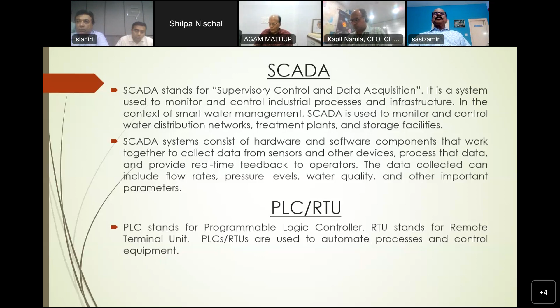A typical SCADA system for a water supply network covers areas like water levels, hydraulic pressure, motor speed and temperature, pumping station ambient humidity and temperature, motion detection, and pump on/off control. All of this is monitored by a Remote Terminal Unit and Programmable Logic Controller, or Intelligent Electronic Device (IED), which through the communication network finally reports to the SCADA master user interface.